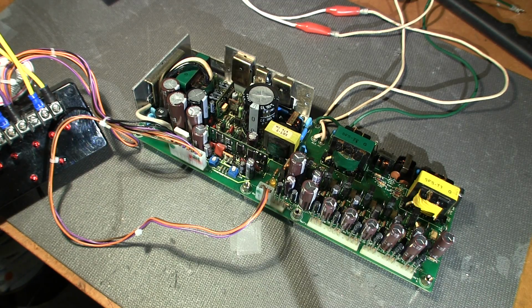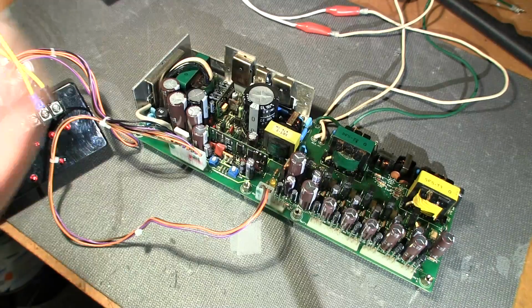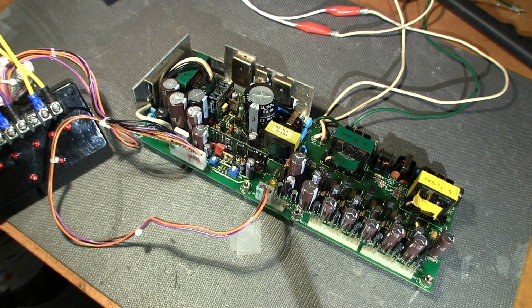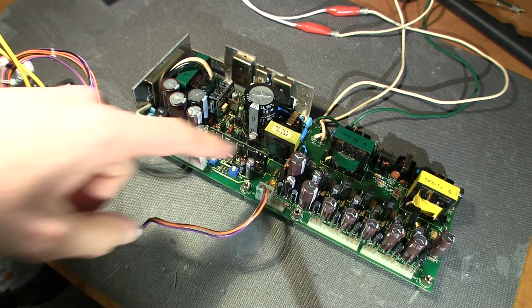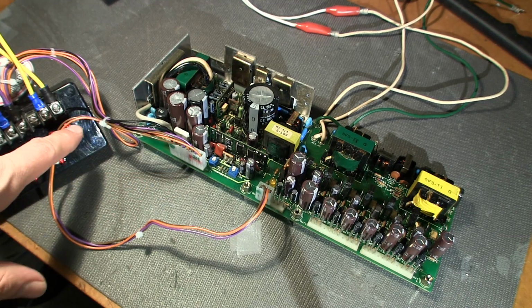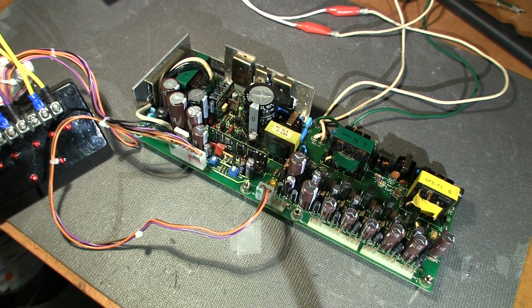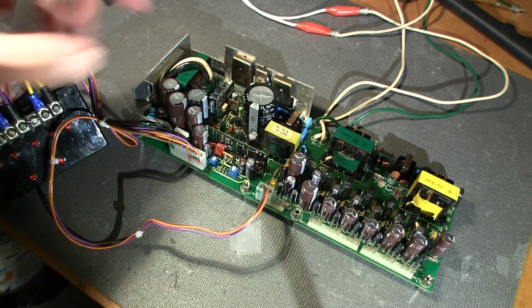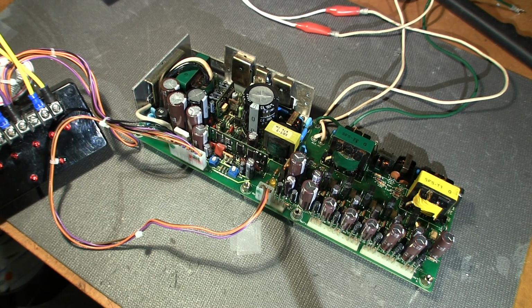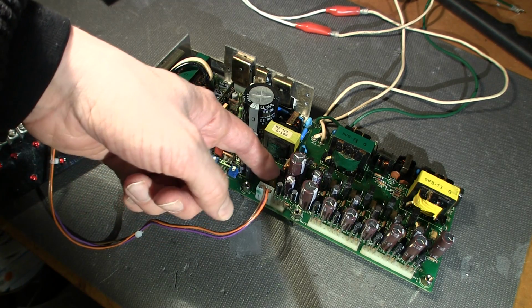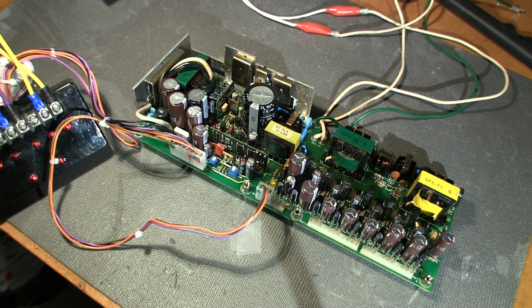In order to easily test this with basically no test equipment at first, I turn on the AC mains. If I see this pulse, or any of the little test fixture LEDs pulse just for a brief second, I know that the startup circuitry is most likely working. If I click on the AC mains and I see no pulse of this little yellow indicator LED or the test fixture LEDs, then I know chances are that startup circuit isn't working. So I'll click on the 200 volt AC mains and we'll see if we see an LED flicker right now.